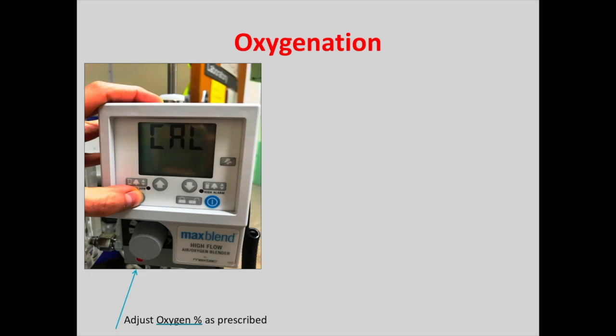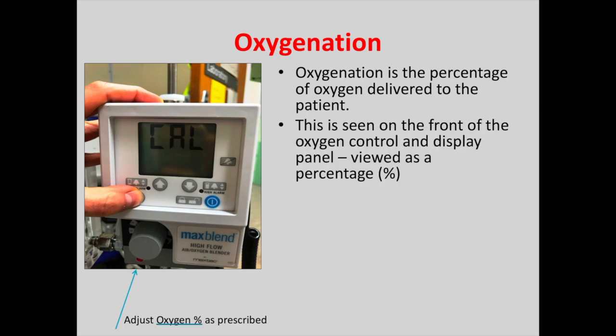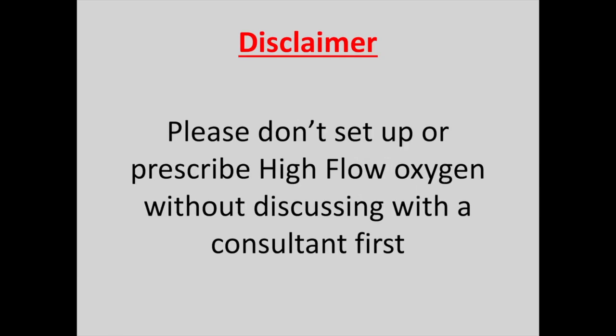Oxygenation is the percentage of oxygen delivered to the patient, seen on the front of the oxygen control and display panel, viewed as a percentage where the calibration sign is shown. Oxygenation can be changed using a dial on the front of the panel where the arrows point. The machine must be calibrated to air before use, done by clicking the up and down arrows at the same time. It's also important to remember that the percentage of oxygen is used in referrals, so this is what we need to know — not just the flow rate.